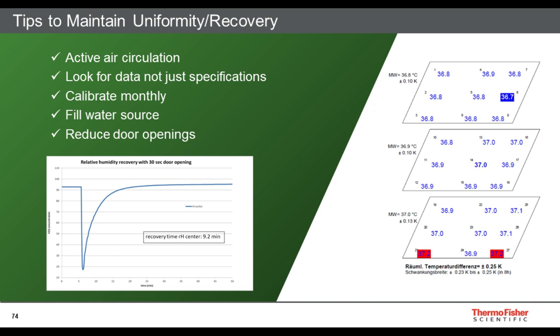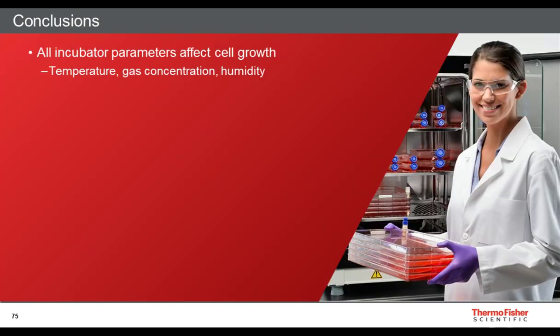So I've got two examples here. On the left is a chart showing recovery of humidity following a 30-second door opening, and on the right is a temperature map showing a 27-point temperature map throughout the incubator chamber. Also, calibrating, of course, monthly will maintain your uniformity and your recovery. As I said earlier, keep the water pan full or the water reservoir, and as always, try to reduce the length and the number of the door openings.